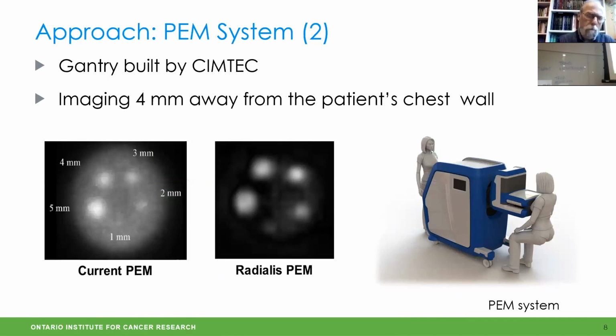The breast is not squeezed like it is with mammography. It doesn't need to be squeezed. In fact, the plates are separated by about 8 millimeters or larger. So basically, they have stabilized the tissue, and then the image is collected. That's an important aspect because we need to be able to get the biopsy mechanism between the plates to access the breast. So the current PEM system now commercially available produces the image on the left, and the Radialis system has a much higher sensitivity, and you can see the result in the second picture. So this is the system we're adding our biopsy guidance to.